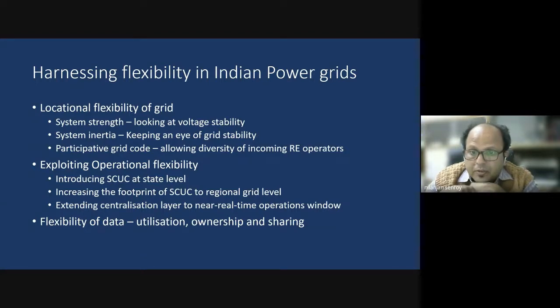The expectations from the incoming independent power producer will be defined in terms of how much active and reactive power reserves have to be provisioned so as to demonstrate their capability to operate under stress. So if the grid code says that if the farm wants to inject 100 megawatts, it should have the capability to inject 50 MVAr of reactive power also. Whether it will actually inject that or not is different, but it should be able to demonstrate that capability.